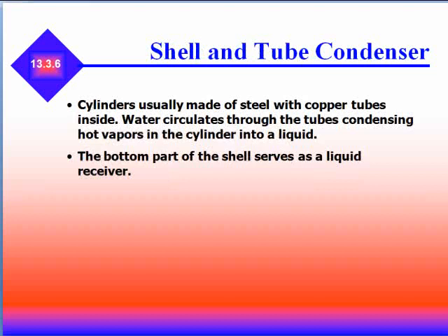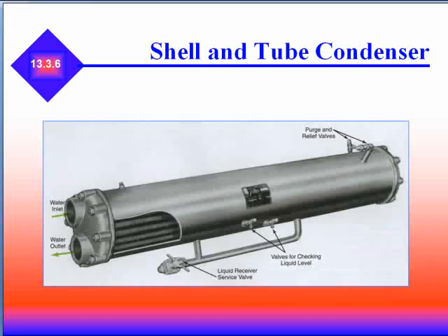In a shell and tube condenser, cylinders are usually made of steel with copper tubes inside. Water circulates through the tubes, condensing the hot vapor in the cylinder into a liquid. The bottom part of the shell serves as a liquid receiver. This is an example of a shell and tube condenser — water inlet, water outlet, and notice the liquid comes out of the bottom.